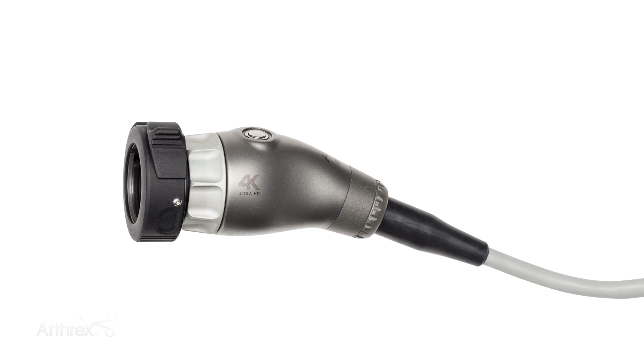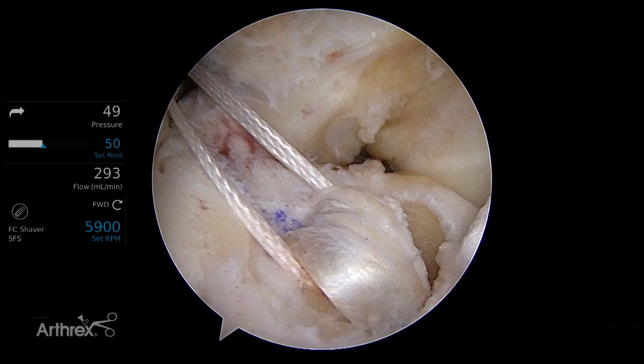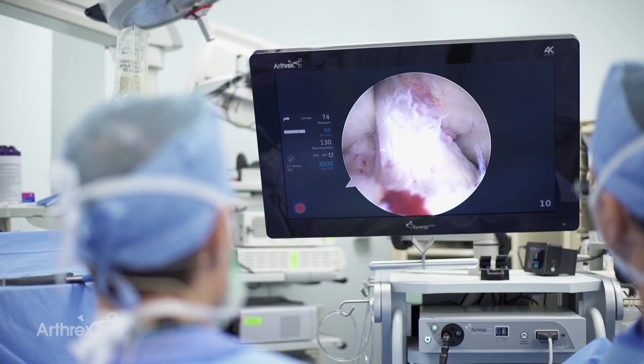So in the camera head design, there's two things that we need to make work. First, we have to get light into the system. And as well, we need to get electronic signals into and out of the system while maintaining this hermeticity. Hermeticity is an airtight seal, something that can withstand the penetrating capability of autoclaving. And a third challenge is enabling user functions so that the camera head is held by the surgeon, of course, in the sterile field, and the surgeon has to enable the proper optical image on the surgical monitor, and as well interact with the device, in particular the camera head buttons that enable the surgeon to take pictures or record video or other things that we enable through the camera system.